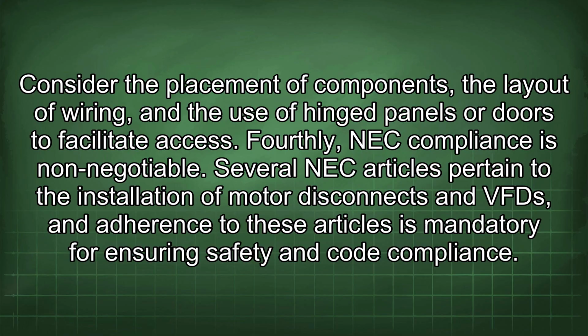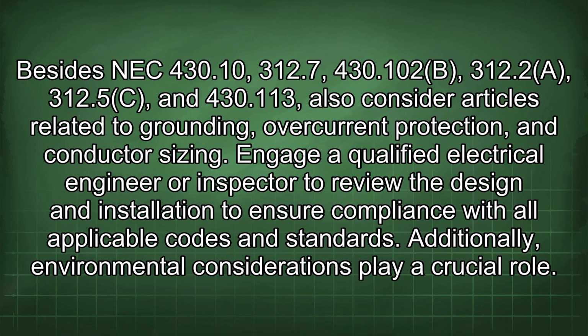Several NEC articles pertain to the installation of motor disconnects and VFDs, and adherence to these articles is mandatory for ensuring safety and code compliance. Besides NEC 430.10, 312.7, 430.102(B), 312.2(A), 312.5(C), and 430.113, also consider articles related to grounding, overcurrent protection, and conductor sizing. Engage a qualified electrical engineer or inspector to review the design and installation to ensure compliance with all applicable codes and standards.